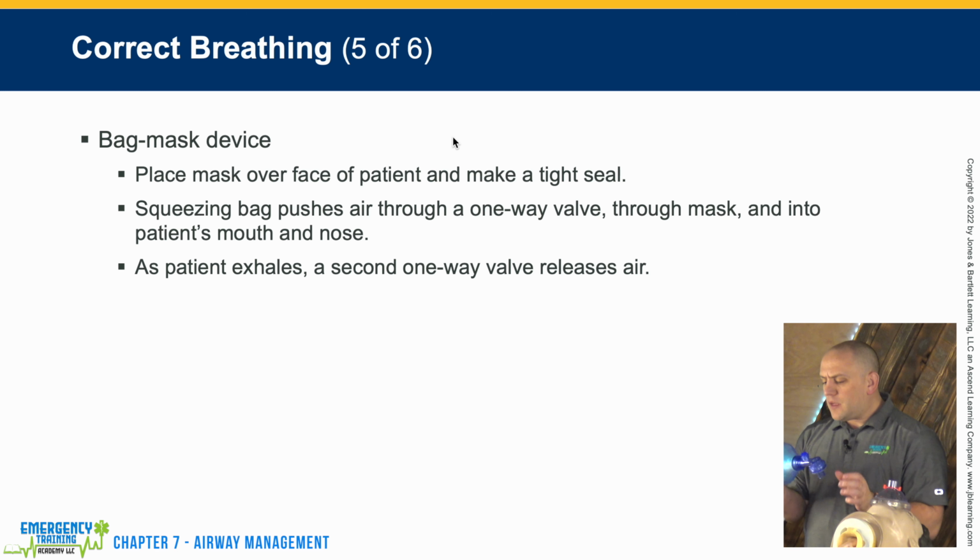It is important to know that these bags hold from 1,800 milliliters to about 2,000 milliliters, and the normal breath size for an adult is between 400 and 600 milliliters. So these bags have a lot more than we need to give to our patients.